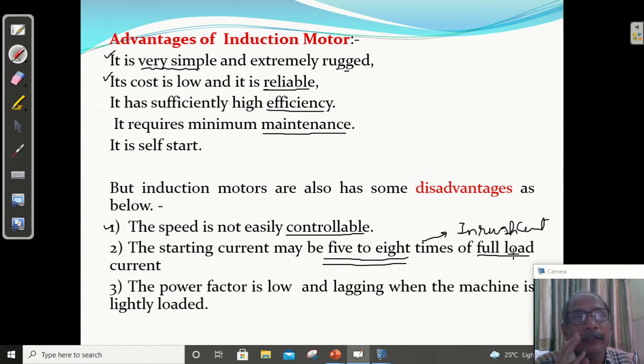Suppose करो we have a 3 horsepower motor and 400 volt 3-phase AC supply. So for a 3 horsepower motor, it may take around 4.5 ampere. That is the thumb rule. What is the thumb rule? It takes nearly approximately 1.5 times of the horsepower rating.